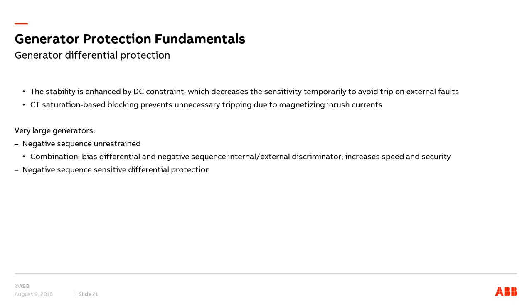And when it comes to large generators, we can make the differential protection more sensitive by using the negative sequence unrestrained differential protection principle. In this case, a negative sequence current based internal or external fault discriminator is used. It enhances the bias differential protection to increase speed and security. The negative sequence current standalone fault discriminator gives a very sensitive generator protection. This option can be blocked for large currents though.